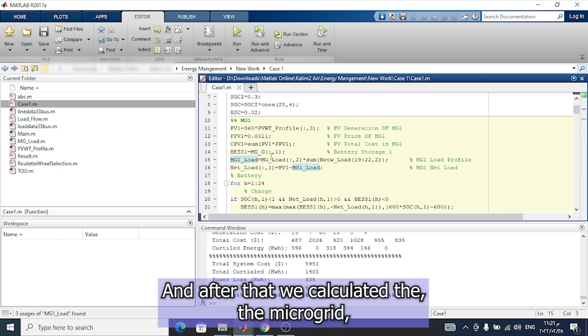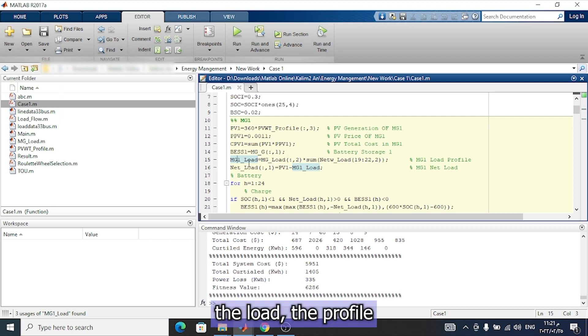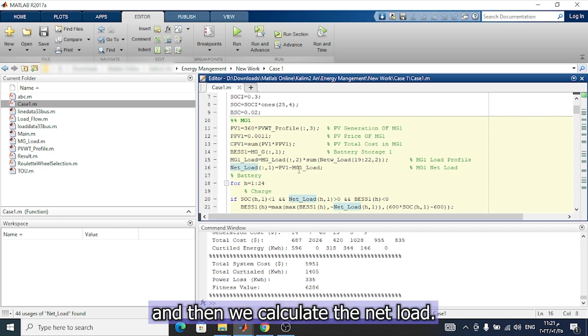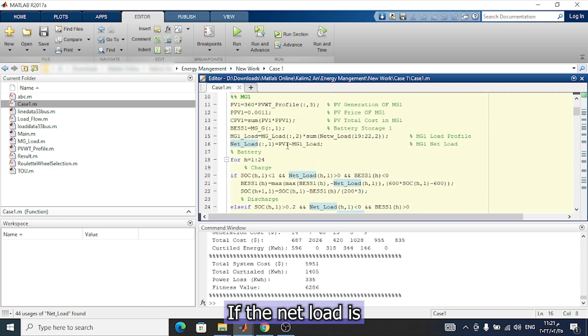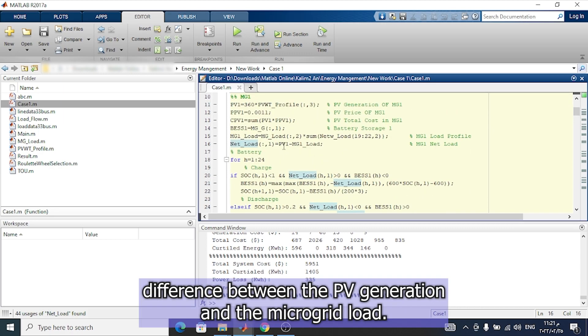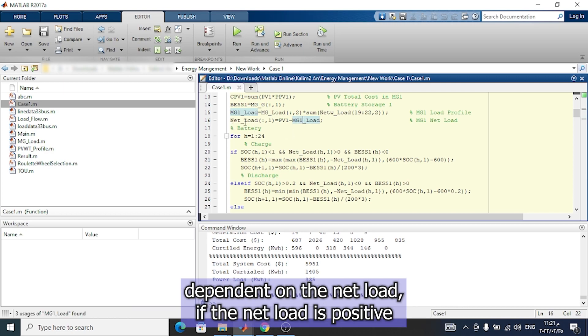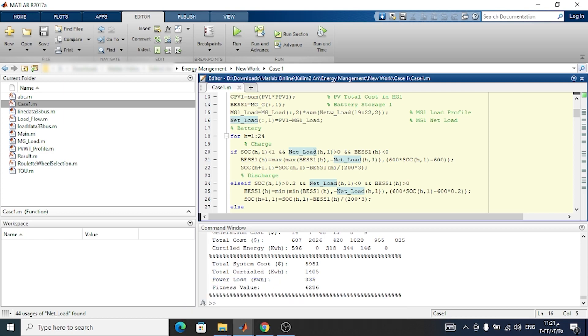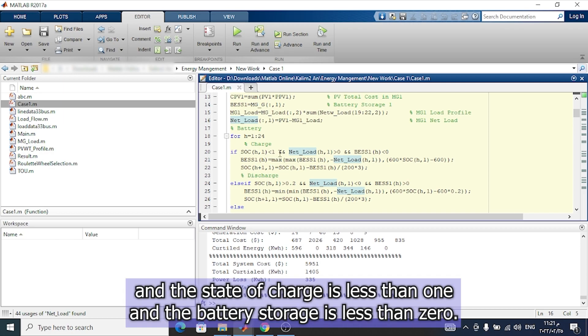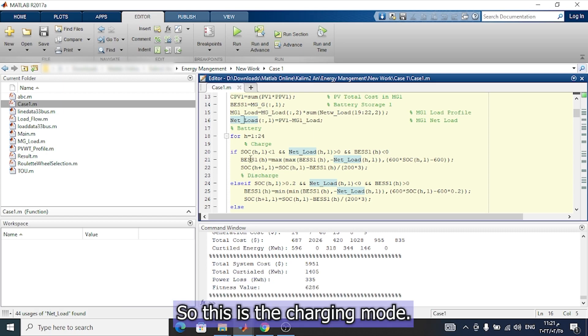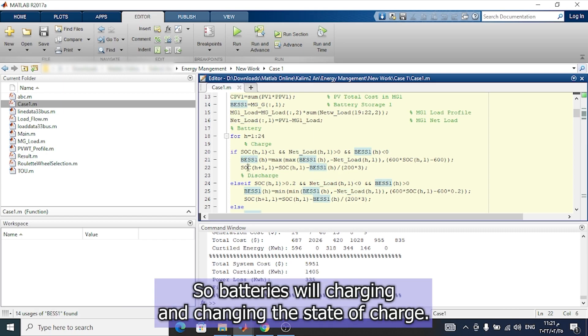We calculate the microgrid load profile, and then we calculate the net load. The net load is the difference between the PV generation and the microgrid load. After that, we decide if the battery should be charging or discharging depending on the net load. If the net load is positive and the state of charge is less than 1 and the battery storage is less than zero, this is the charging mode — the battery will charge and the state of charge is updated.